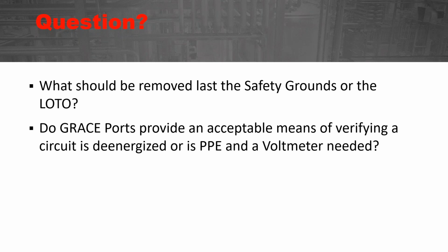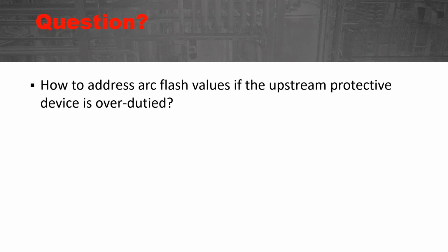Thanks, Jay. And the next question is, do GRACE Ports provide acceptable means for verifying a circuit is de-energized? I think Charlie mentioned it several times. So we have a voltage test station and also a safe test point where you can verify the de-energized state from outside the door, so you can minimize the use of PPE and such. So let's go to the next question.